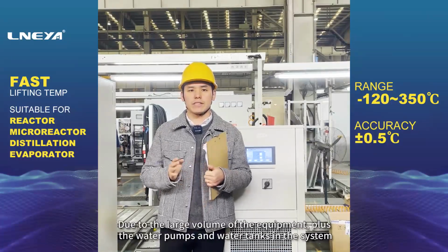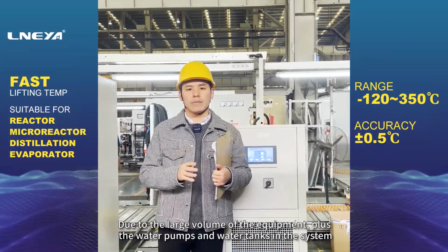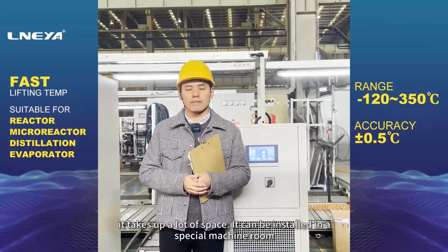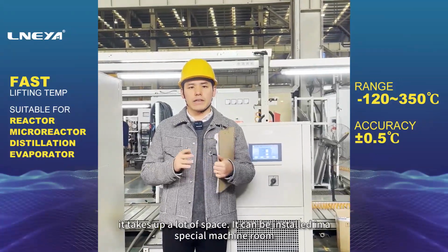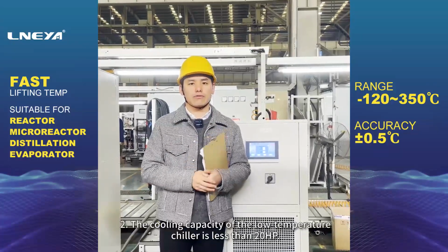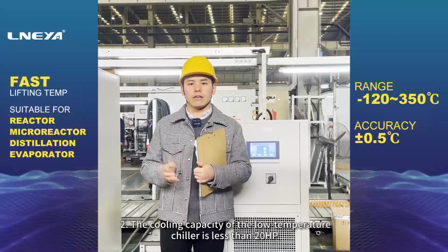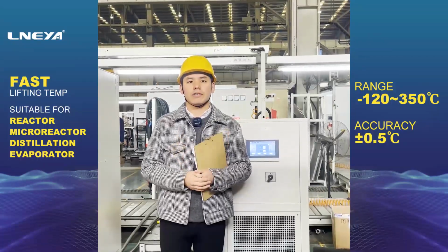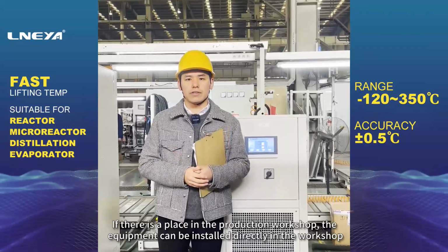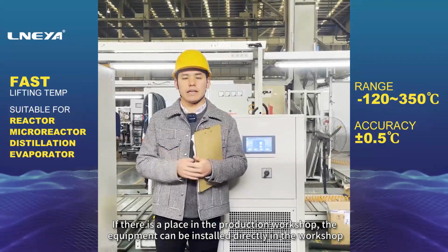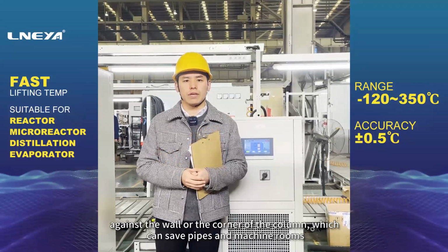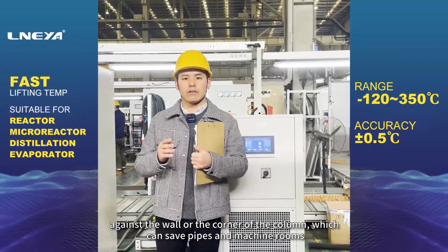Due to the large volume of the equipment, plus the water pumps and water tanks in the system, it takes up a lot of space. It can be installed in a special machine room. Second, the cooling capacity of the low-temperature chiller is less than 20 HP. If there is a place in the production workshop, the equipment can be installed directly in the workshop, against the wall or the corner of the column, which can save pipes and machine rooms.